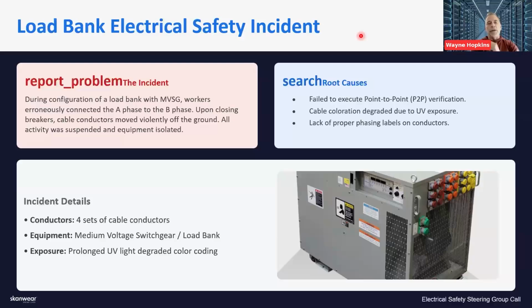On the incident details, again there were four sets of cable conductors on this medium voltage switchgear they were load banking. The cable conductors - A phase, B phase, C phase - are typically color coded, as most of you know. But these sit out in the sun all day, and UV light can fade the labeling and coloring, which is what happened in this case.